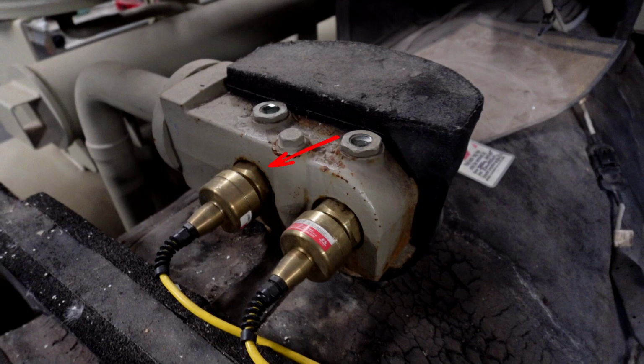Now that also means that these need to be calibrated and able to function simultaneously. In a perfect world, these operate perfectly together and they remain in the same position as they stroke back and forth to control flow. But that's not always the case. Sometimes as these valves begin to fail, one can get out of calibration compared to the other, and then one has to open way up while the other one may be stuck or isn't opening like it needs to, so the other one has to try to compensate for it, which can then lead to just overall flow issues.